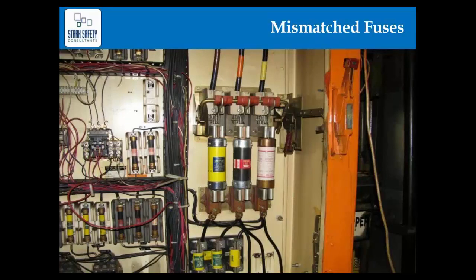A very common issue is mismatched fuses. You should have a plan in place before starting field verification to address how to handle mismatched fuses. Ideally, you'd consolidate the fuse types to make them all the same while you're in there, but you may have to shut equipment off to do that, which may not fit your scheduling. So it's important to have documentation of which devices need this done, and if you can get the fuses consolidated before finishing your model, that's most advantageous.